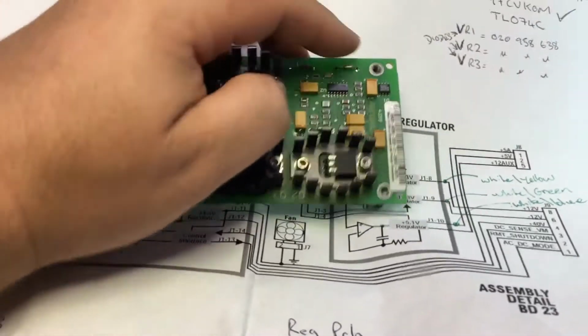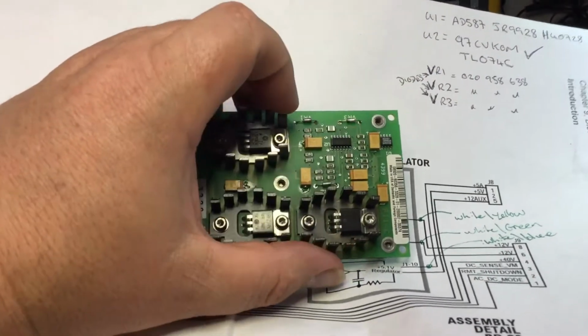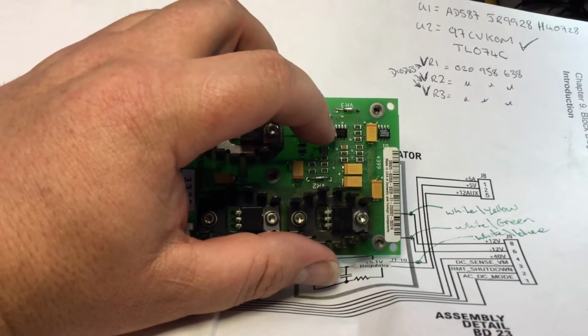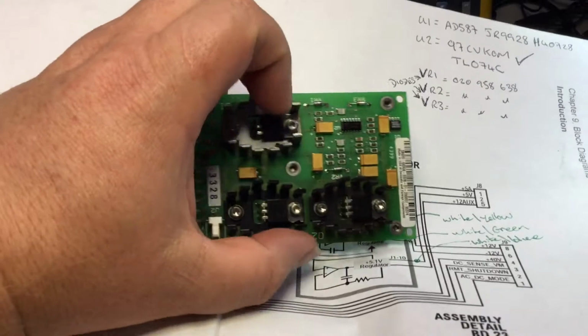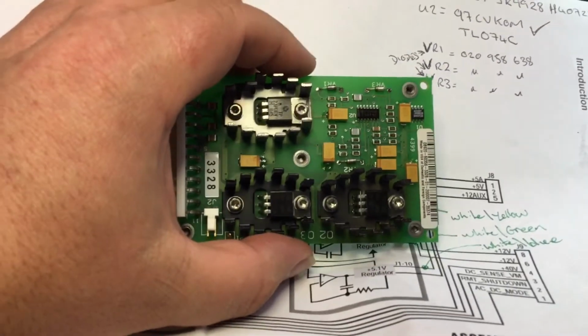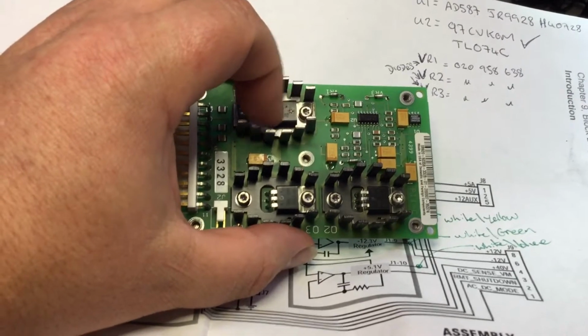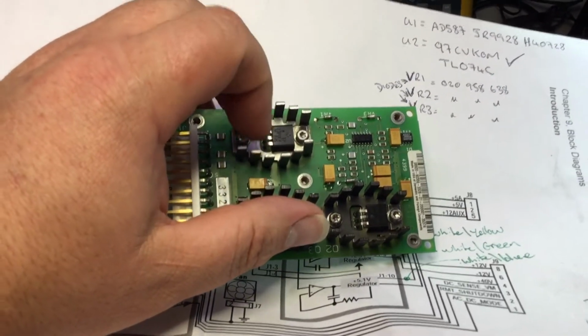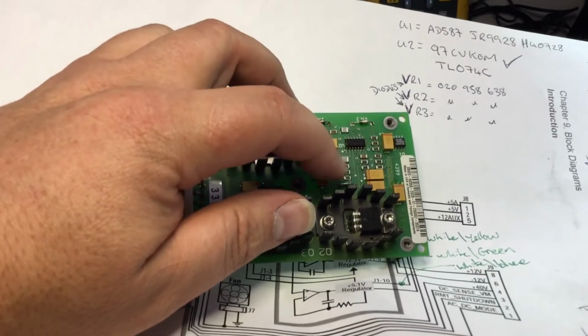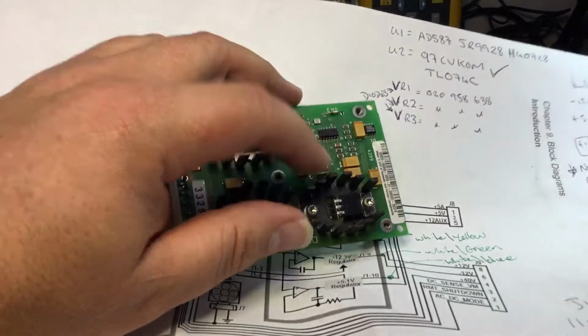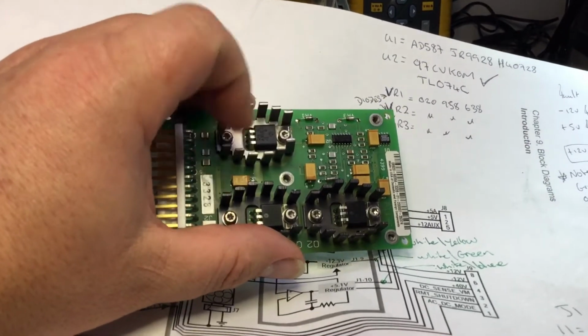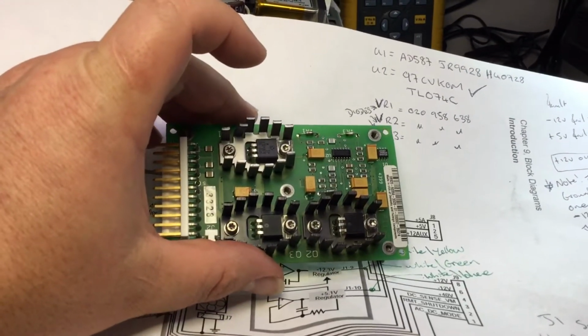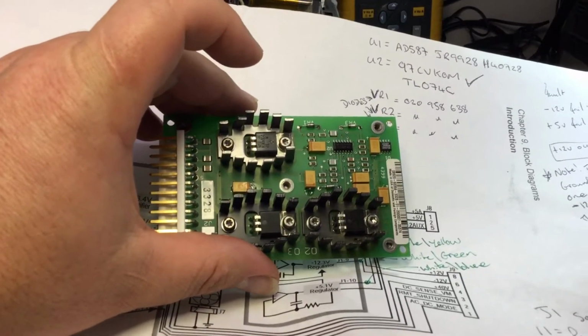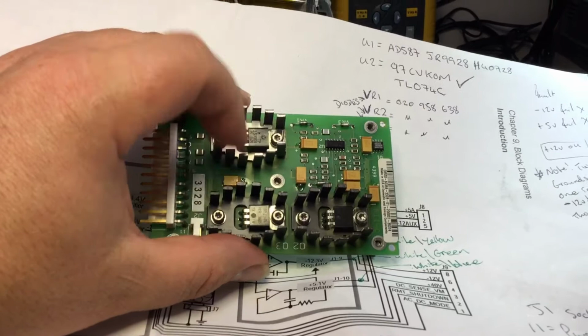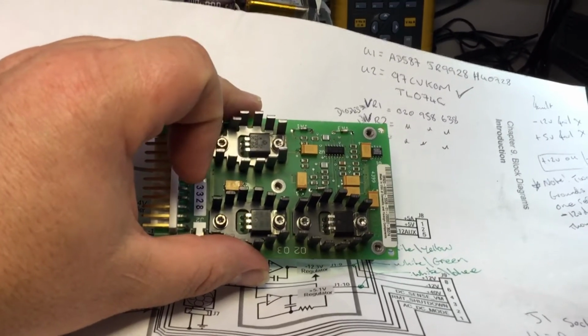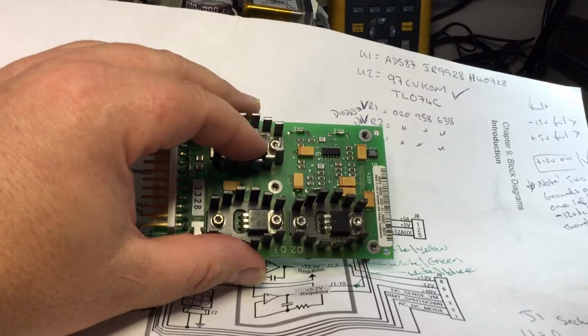We've got a precision reference here, 10 volts, that was working okay. This is the driver IC for these regulators, and that appeared to be functioning. The 10 volt reference was supplying the right biasing conditions to these regulators, but it didn't seem right - there was no output, but there was an output if there wasn't a load. So with just the high resistance of the DVM measuring the outputs, there was a supply voltage there, not what it should be, but near enough.